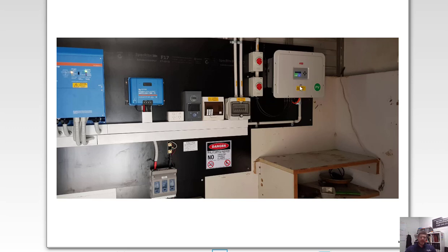How this AC-coupled inverter works is that it only works when there's a grid, and you've only got the amount of usable power available from your solar panels. For this customer, they're completely off-grid — their grid is just a generator. This inverter only operates during the day, which is the most efficient setup. Solar panels come in, go DC into AC, and directly power all the house loads. Any excess goes over to the inverter charger, which then takes that AC, turns it into DC, and charges your batteries.